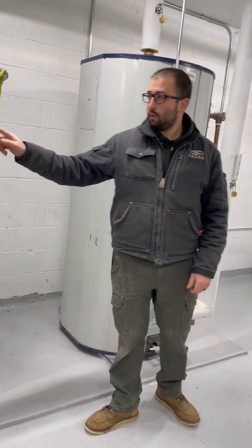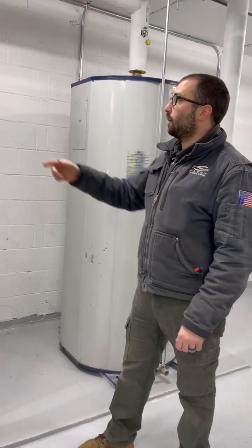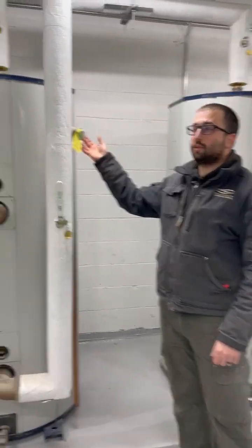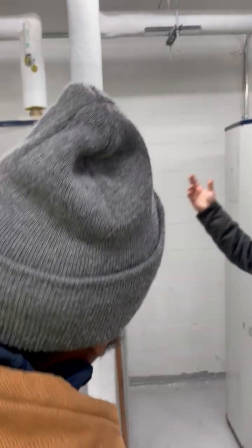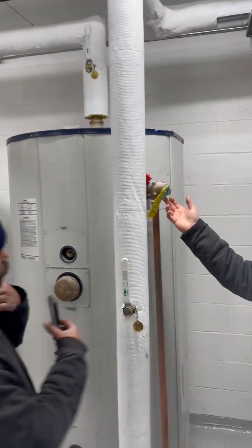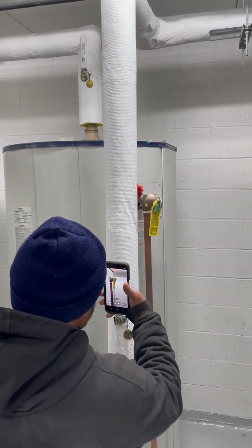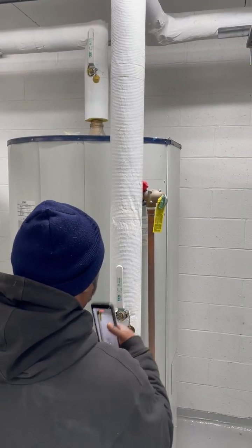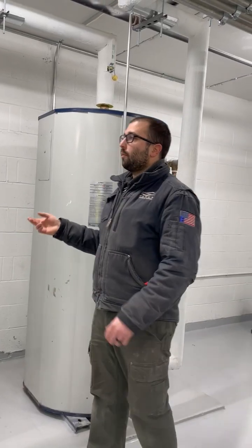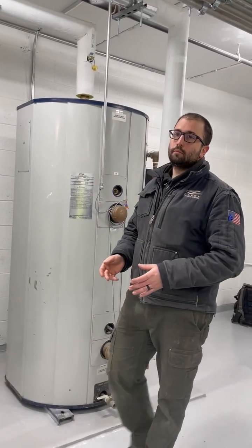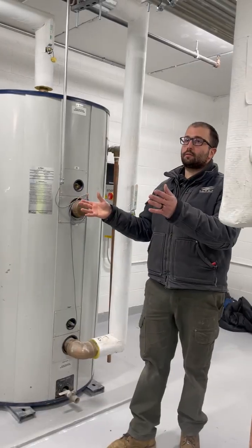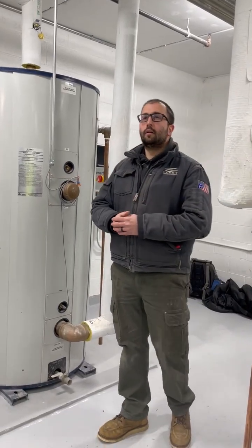One thing I'd recommend having in building stock is maybe 1 or 2 of these T&P valves. Sometimes people come up here for whatever reason and open this. T&P stands for temperature and pressure relief. It's supposed to blow off at 210 degrees Fahrenheit and 150 PSI. Usually that'll kick in to save the equipment, right?